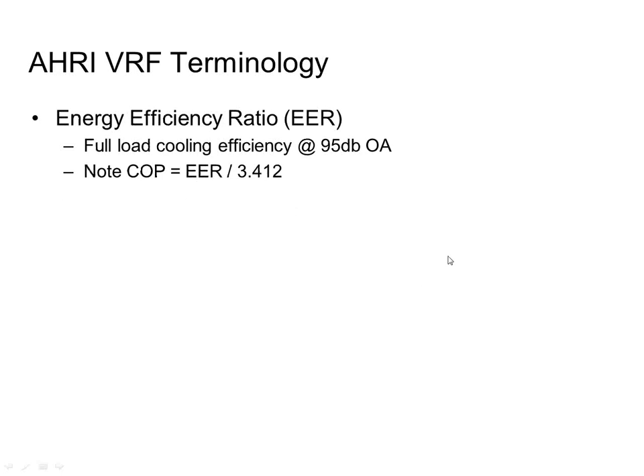The next thing you'll notice on this data is the EER, energy efficiency ratio, which we had mentioned. This is the rating system that we use for lots of different types of cooling equipment, and it's tested at full load cooling, which basically means we run the unit full maximum at a steady state condition, and it's tested at 95-degree dry bulb. If your location only needs 89 degrees or you need 110 degrees, oh, sorry, we'd only test them at 95, is kind of the thing there. So it's really good for comparing one to the other, but it doesn't really tell you what's going to happen at your location.